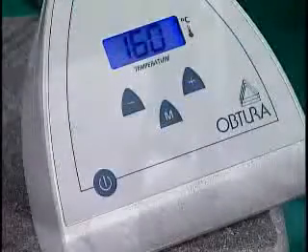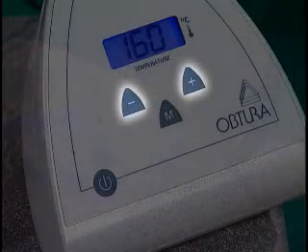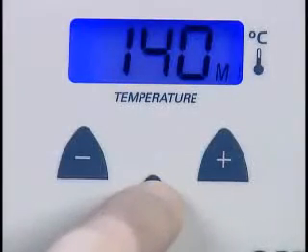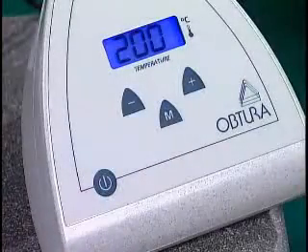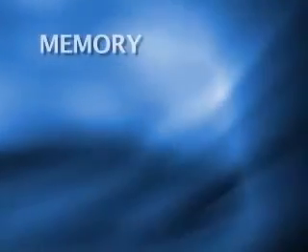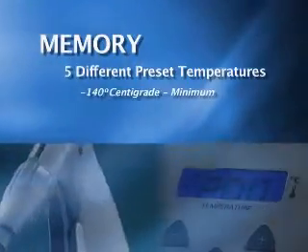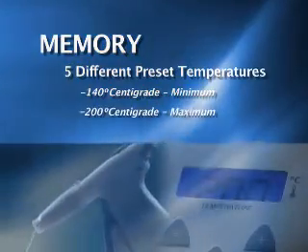The key benefits of your new Obtura's control panel are push-button digital temperature control for more accurate reproducible settings and a memory function that stores up to five user-selectable heat levels. Pressing the power button activates the unit with the LCD digital readout showing the last used set point. The Obtura comes with five different factory preset temperatures, starting with a minimum of 140 degrees centigrade to a maximum of 200 degrees centigrade.